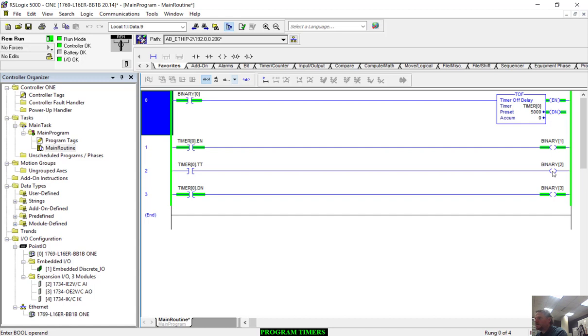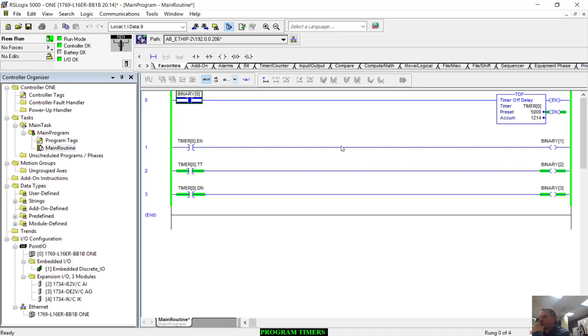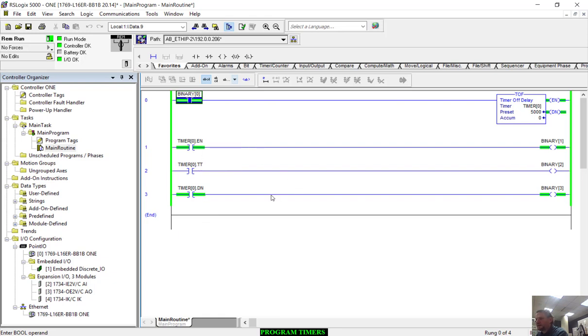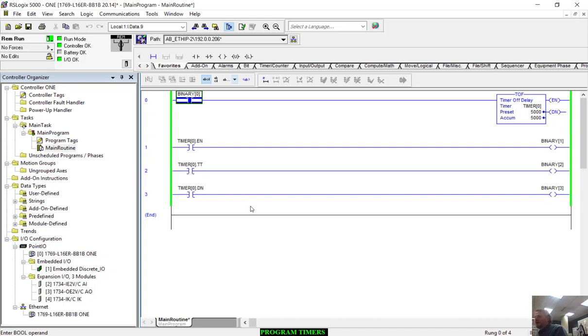Control T. So now we're seeing the timer timing and done bit is off as soon as that done bit turned off. As soon as we hit five thousand, so let's do that real quick again. Enable's on, timer done's on. Enable is going to turn off, timer timing is going to turn on. Just like that. And then as soon as it hits five thousand, these two bits drop out.